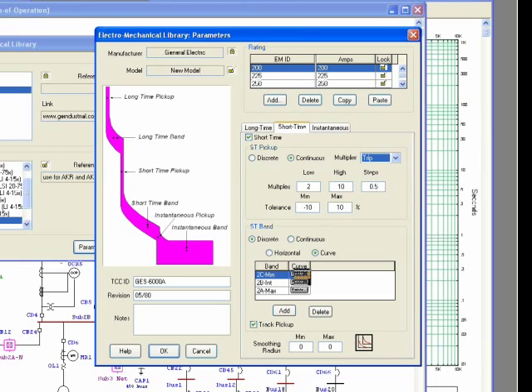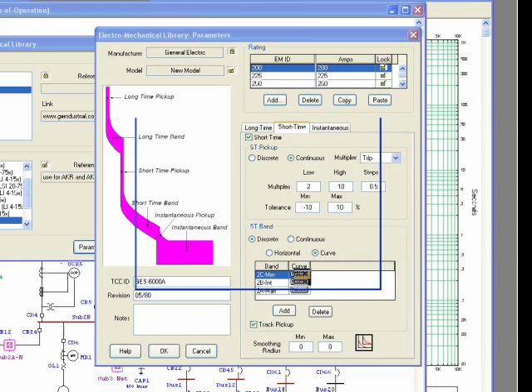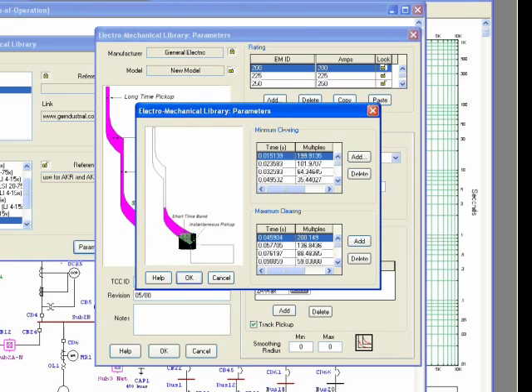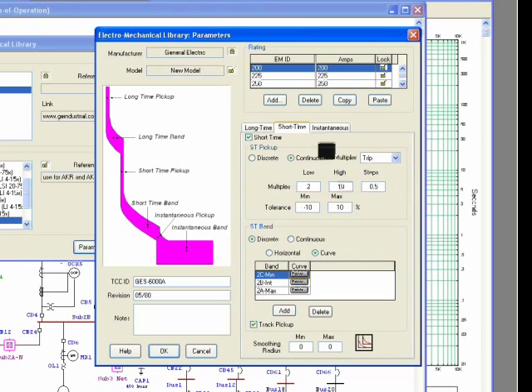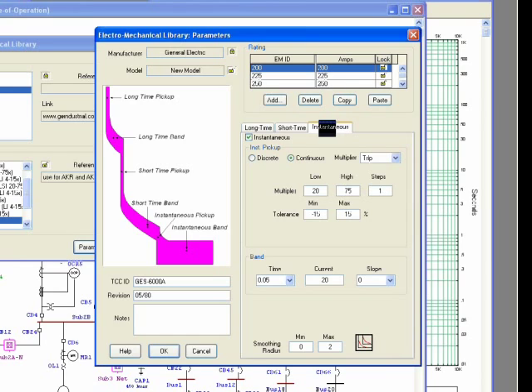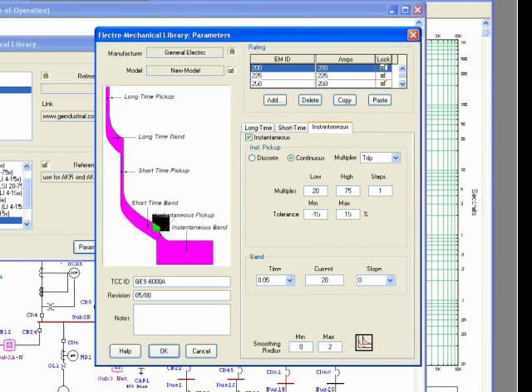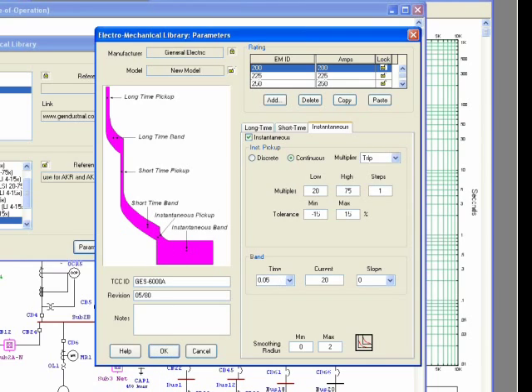So the curve characteristic can be entered through this editor, same concept as long time, but in this section you are focusing on this area. And then the next level is called instantaneous. Instantaneous is normally the vertical line at the end point of the curve, and you can specify the band, the horizontal part at this area.